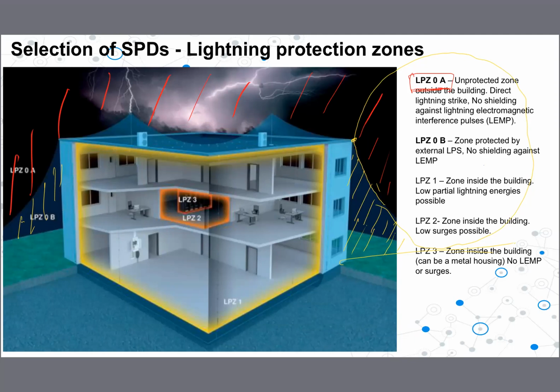So then we have another zone, LPZ 1, zone 1, which is inside the building. Therefore, it is covered against direct lightning, but it is not fully secured against induced effects. If there is a lightning strike somewhere here, the voltage can induce inside as well. It is not fully covered against LEMP. Then zone 2, a place like this within the installation, which is covered by the lightning protection, as well as having very low impact due to induced voltages, meaning very low impact from electromagnetic interference.